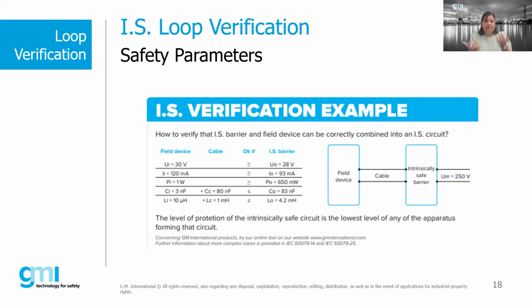And this is the maximum amount of energy it can pass into the field in normal or abnormal situations. So pretty much the rule is, if my device can handle 30 volts, I need to make sure my barrier will pass 30 volts or less, right? Because if I pass 31, I'm going to break the field device.